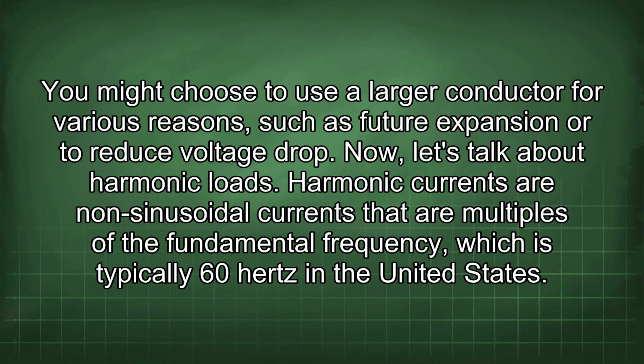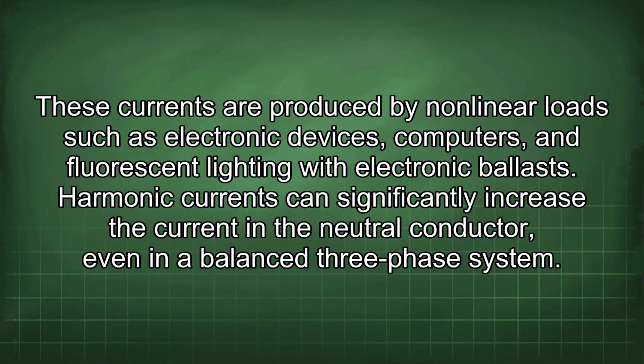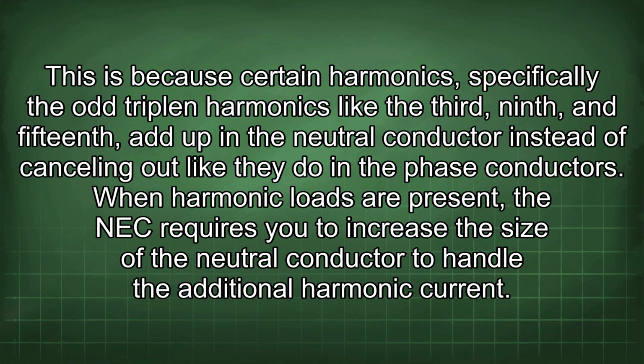Now, let's talk about harmonic loads. Harmonic currents are non-sinusoidal currents that are multiples of the fundamental frequency, which is typically 60 Hz in the United States. These currents are produced by nonlinear loads such as electronic devices, computers, and fluorescent lighting with electronic ballasts. Harmonic currents can significantly increase the current in the neutral conductor, even in a balanced three-phase system. This is because certain harmonics, specifically the odd triplen harmonics like the 3rd, 9th, and 15th, add up in the neutral conductor instead of cancelling out like they do in the phase conductors.